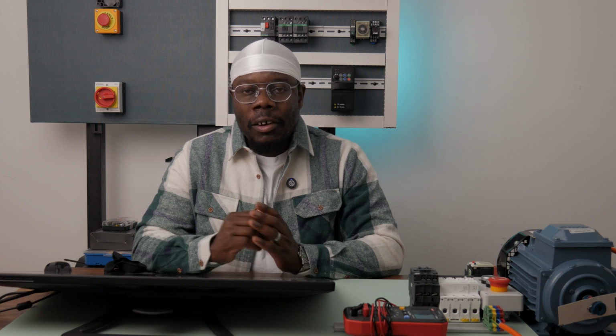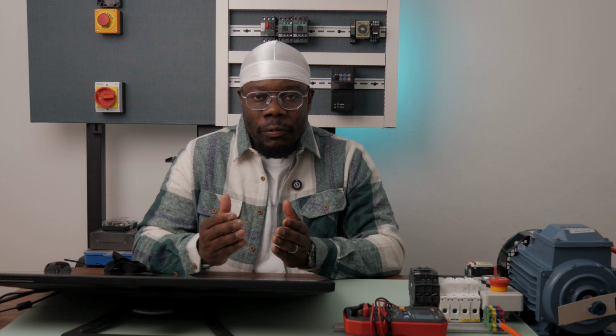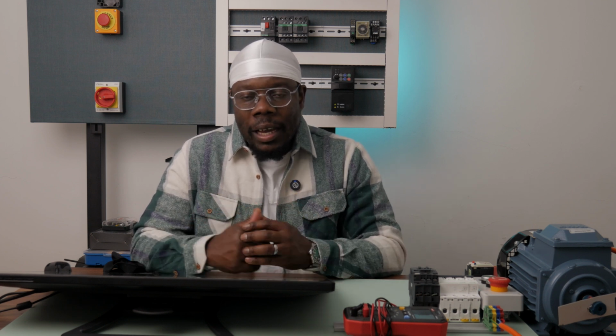Now, due to the high inrush currents of direct online motor starters, the use of direct online starters is generally limited to electric motors of sizes around 7.5 horsepower up to maybe around 10 horsepower. And beyond that, you should start using other methods like reduced voltage starters, for example, the Star Delta or soft starter or variable speed drives. But you can always check your local codes for the specific limits of your country.